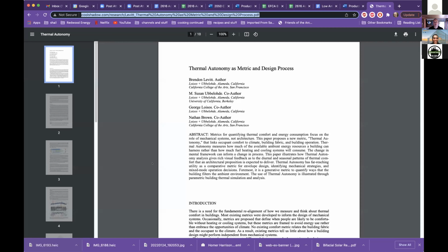And it's actually surprisingly long. If you start doing the energy modeling, you can get a building to float several hours before you need to do something to it. The more mass there is that's exposed, the longer that is. And if you want to go crazy, do a heavy mass radiant slab. You can get almost 24 hours of load shift out of a radiant slab that you pre-inject the day before. There's a whole bunch of fun stuff you can do. It's all in the controls.